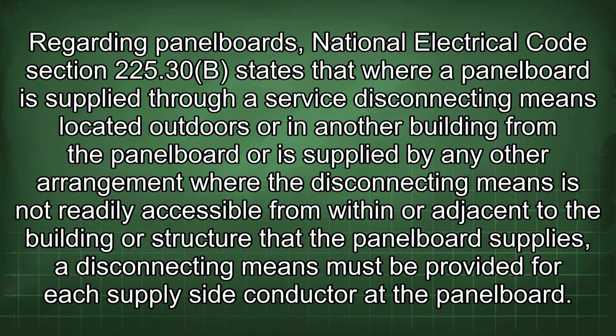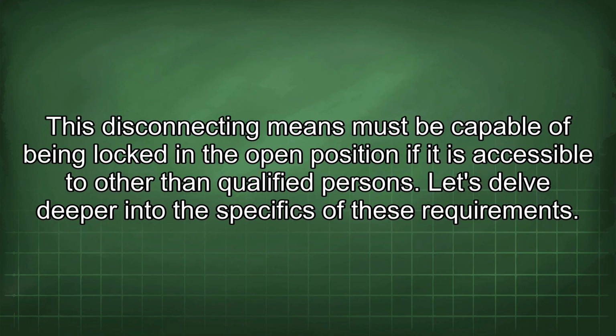Regarding panel boards, National Electrical Code Section 225.30(B) states that where a panel board is supplied through a service disconnecting means located outdoors or in another building from the panel board or is supplied by any other arrangement where the disconnecting means is not readily accessible from within or adjacent to the building or structure that the panel board supplies, a disconnecting means must be provided for each supply-side conductor at the panel board. This disconnecting means must be capable of being locked in the open position if it is accessible to other than qualified persons. Let's delve deeper into the specifics of these requirements.